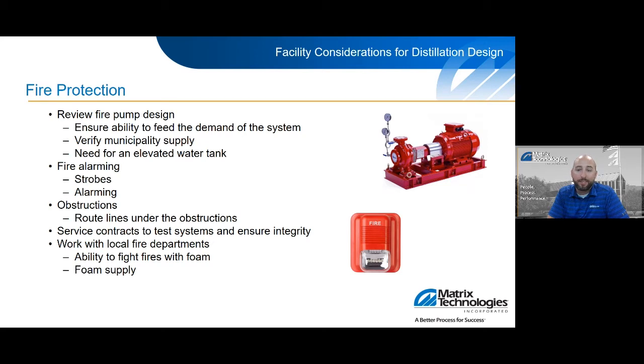Another thing to consider is your fire alarming and your strobes. It often gets overlooked in the process, but it's important to make sure that you install this to alert your staff in the event of a scenario. Again, work with your architect and your fire suppression engineer to make sure that these are located in the proper locations. Obstructions are another thing to take into consideration too. Tanks, I've seen fireheads dropped below tanks or low spaces that are big enough to occupy somebody, but a space you wouldn't go into, not necessarily a confined space. But depending on what those are, you may have to locate unique sprinkler heads in your facility. And again, be sure that your equipment's serviced and maintained to meet the facility's needs, and keep records of those testing requirements for your own use and for your insurance company's use.